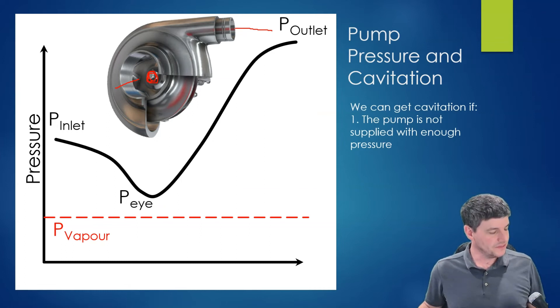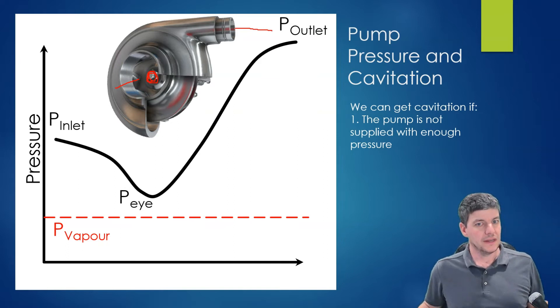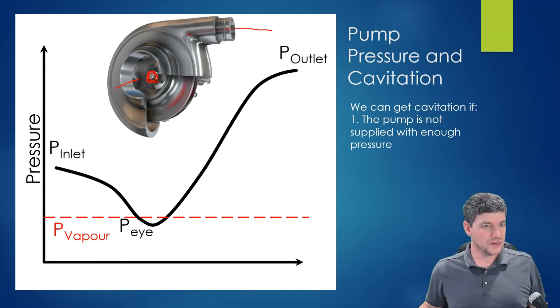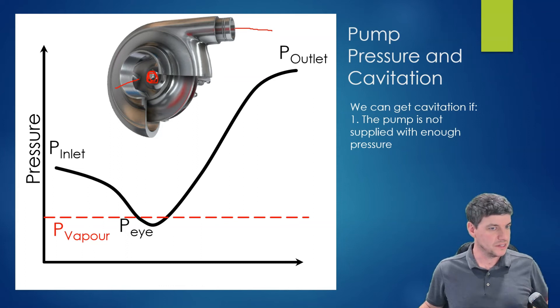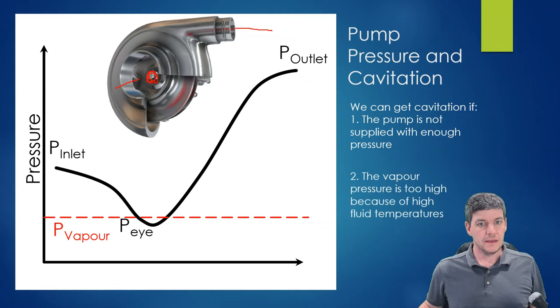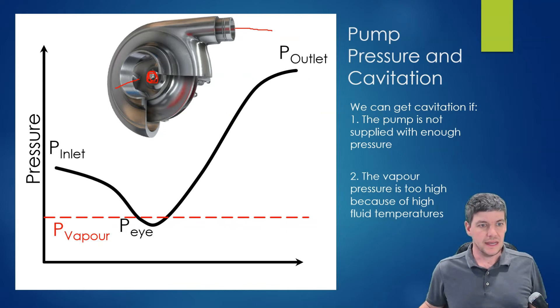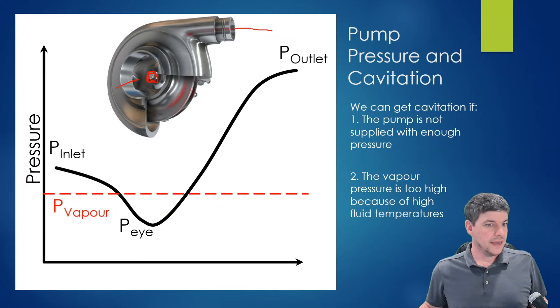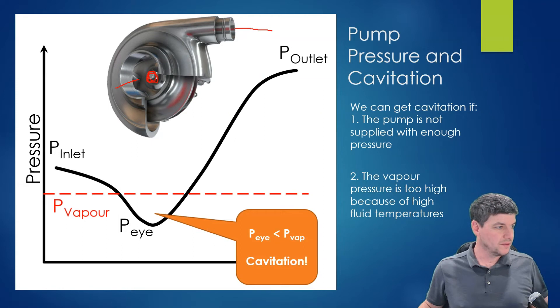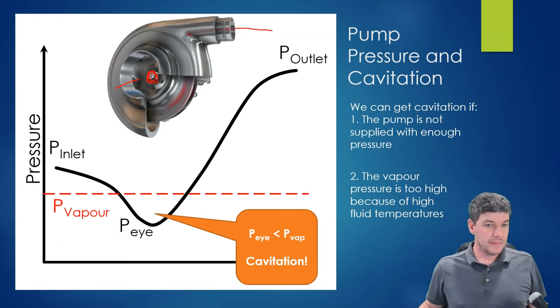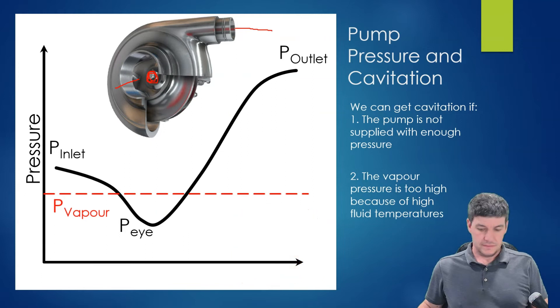Cavitation can occur in a few different cases. First, if we don't supply the pump with enough starting pressure, the entire pressure curve shifts down and the eye dips below the vapor pressure. Second, if the fluid temperature is higher than expected, the vapor pressure rises, and again a section of the pressure curve may drop below the vapor pressure, causing cavitation.